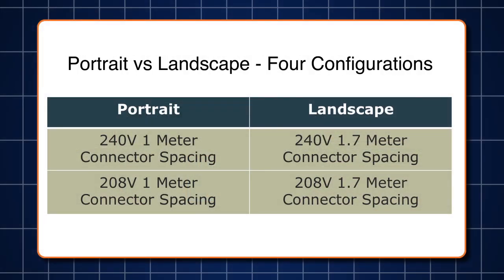The cable is available in four configurations: portrait or landscape, and 240 volt or 208 volt. The portrait cable has connectors 1 meter or 39.4 inches apart, while the landscape cable connectors are 1.7 meters or 66.93 inches apart.